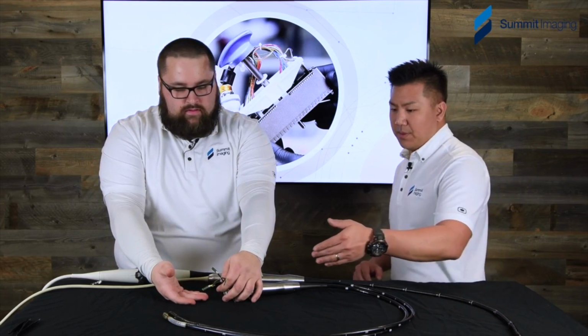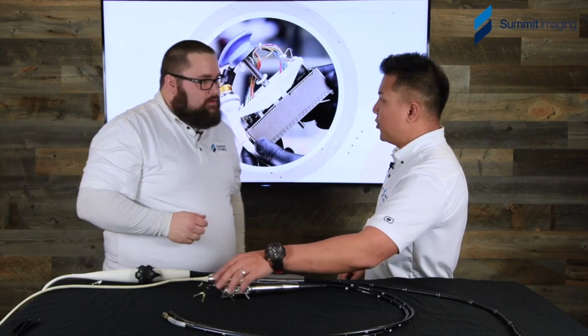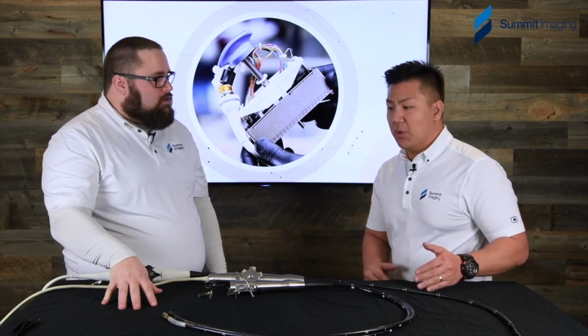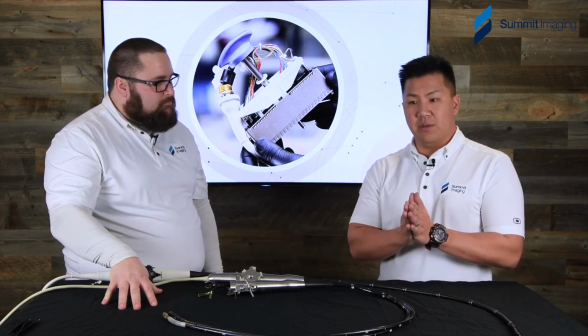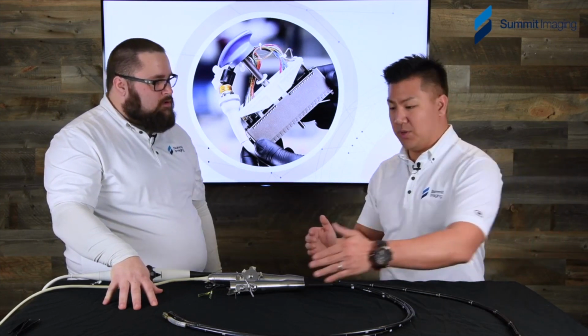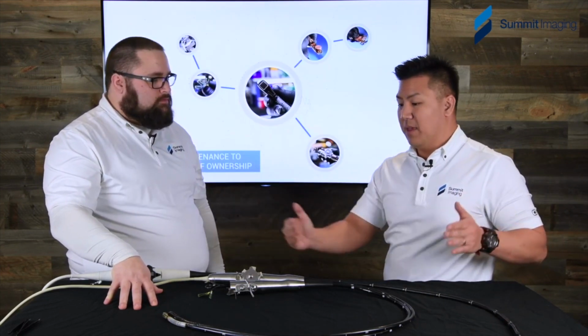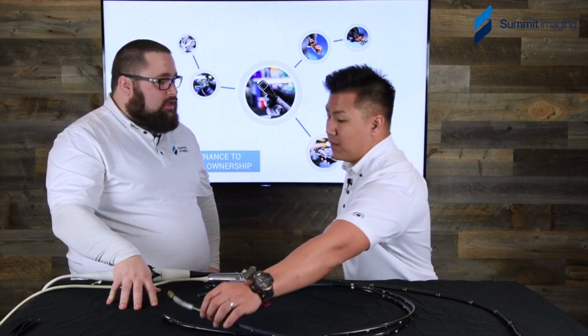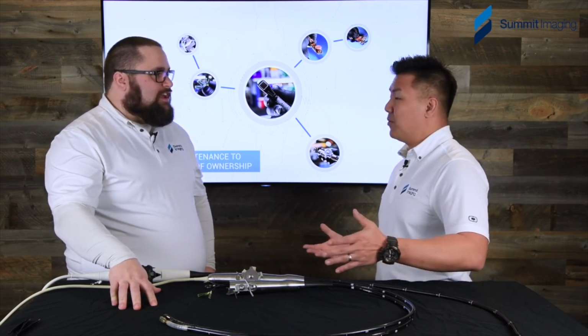Okay? And it's also key to say here that when there's fluid intrusion here, because when you look at the entire transducer being giant circuits that are going to the array and coming back to the system, that fluid intrusion here is nearly the same symptoms as if the fluid intrusion occurs here at the tip. Oh, exactly. Because you are shorting and frying the circuit, and the machine doesn't really care or interpret where the short or the open is, where it's not supposed to be. It just sees that this channel has a failure, and it's going to represent a bad image at that point.